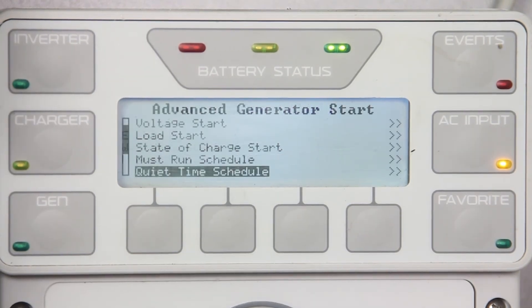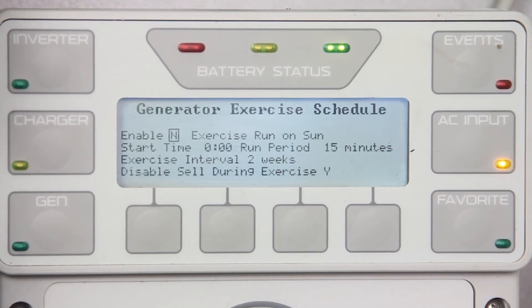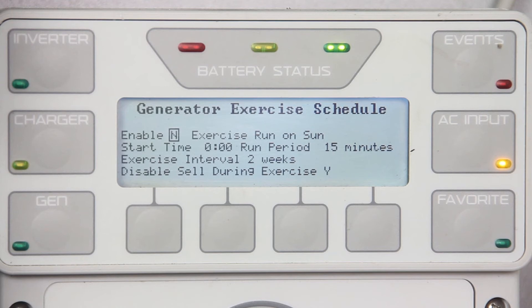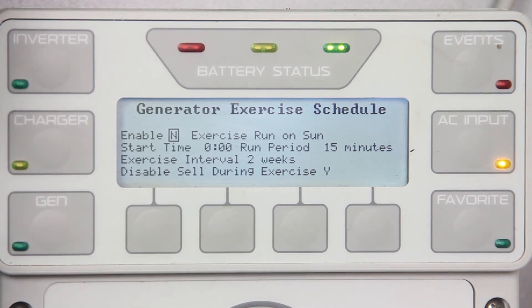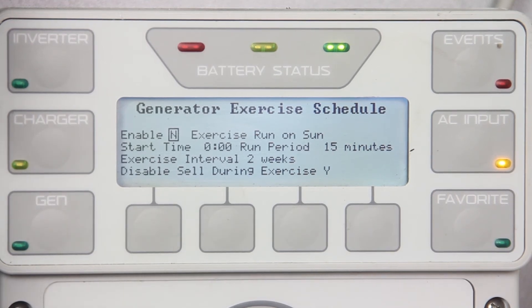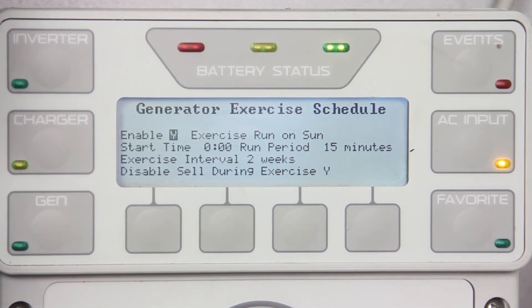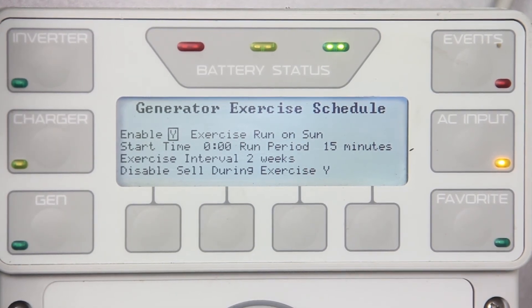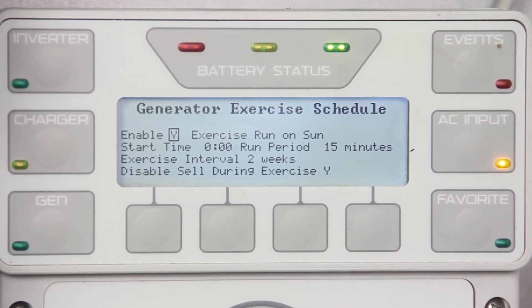Press up once and scroll down to generator exercise schedule. Exercise is a period of time when the generator is scheduled to run briefly. Consult with the generator manufacturers for the appropriate length and frequency of exercise periods. To enable, change the N to Y and enter the desired start time, run period, and interval between 0 to 8 weeks.